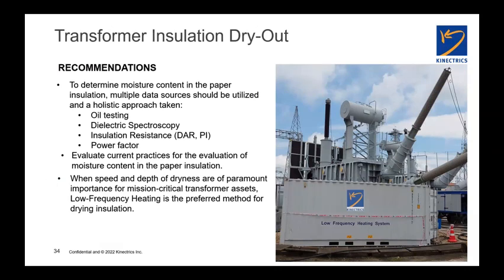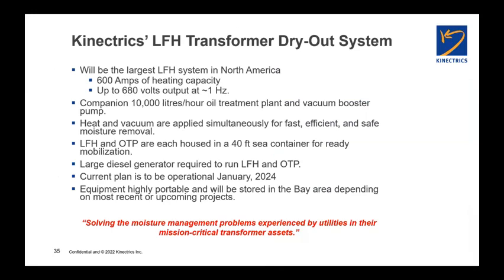As a recommendation for big high voltage units, where time is a limiting factor, like an outage at a generator plant or a nuclear power plant, we look at low frequency heating as the preferred drying method. And we are in the process of acquiring what's going to be the largest low frequency heating system in North America. We actually have a smaller unit that we call Mini-Me already. This one's going to be considerably larger, and it'll be capable of drying transformers in the 1000 MVA 3-phase range. So we will be addressing wet units in 2024.